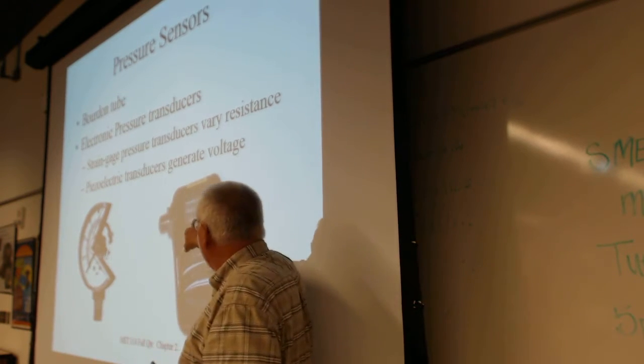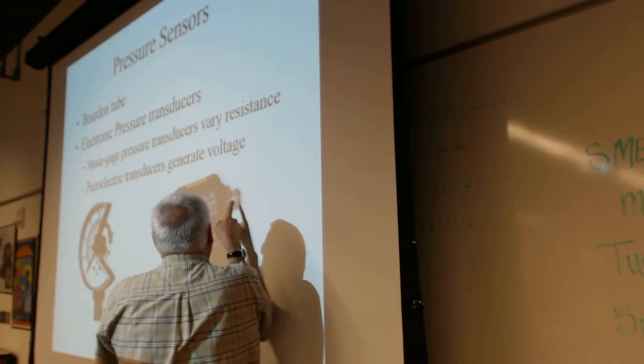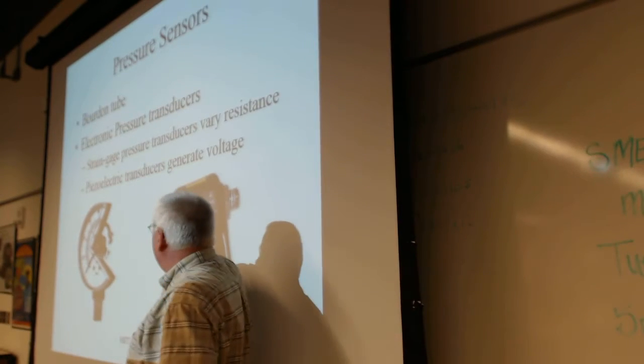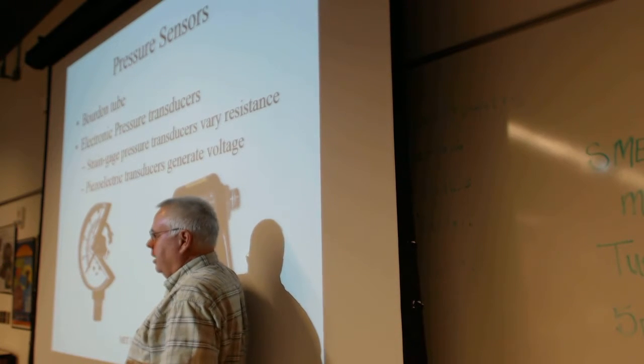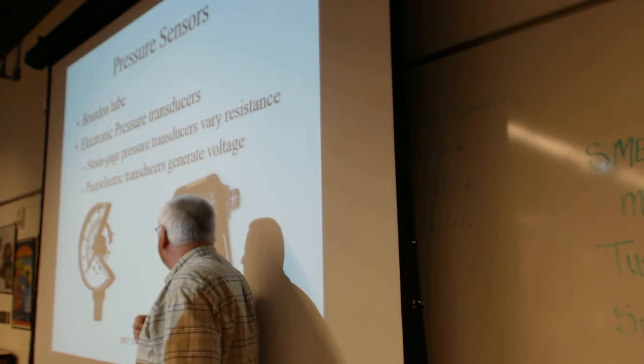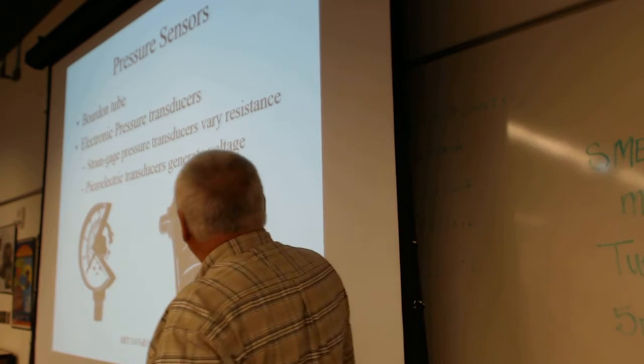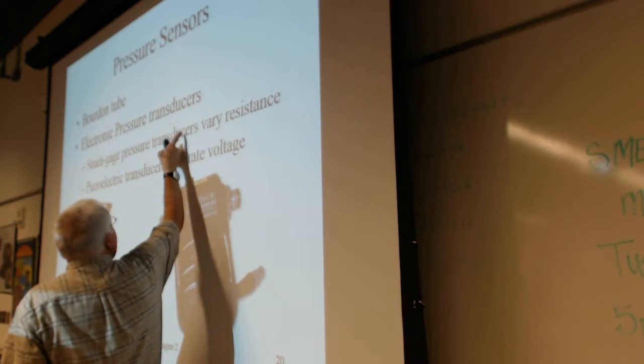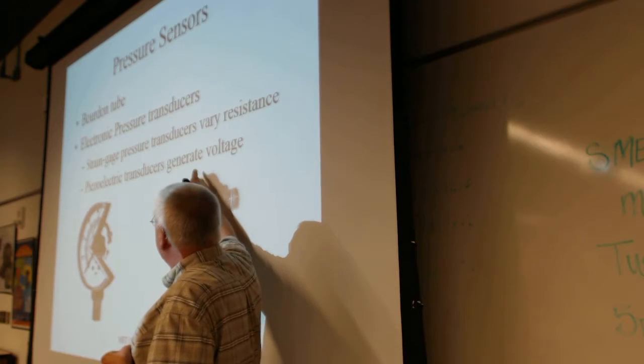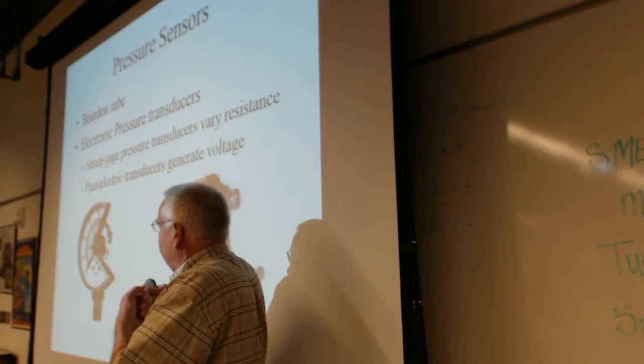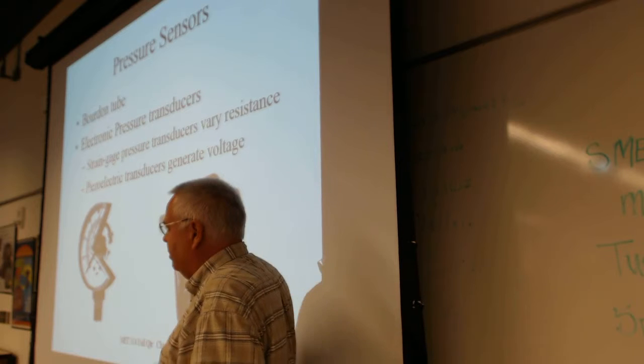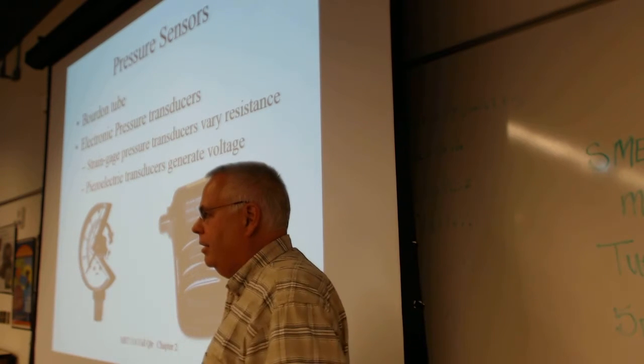The electronic ones like this - we'll use some just like this. Here's the differential gauge - the difference between this pressure and that pressure. Leave it open, put the pressure here, and it just reads gauge pressure. Depending on whether it's a strain gauge on the diaphragm - a strain gauge would change resistance as it stretches - or a piezoelectric transducer will generate a voltage when it gets squished. Usually all that gets handled by electronics inside. You don't have to worry about it, it will just read you out a value.